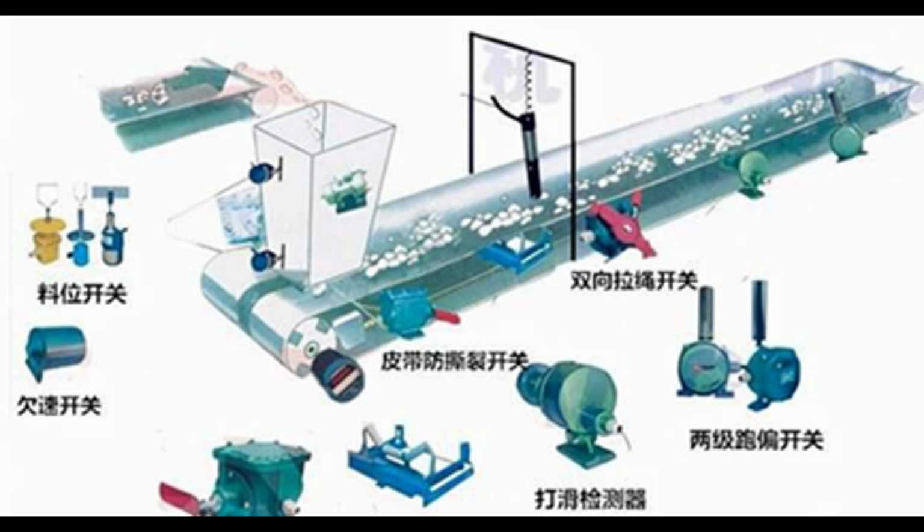3. Anti-tear protection device. An anti-tear protection device should be installed 10 to 15 m below the belt blanking point in the direction of the machine head when the head is driven. It is installed between the upper and lower layers of the conveyor belt, and the protection mode is piezoelectric or traction wire rope type. When longitudinal tearing occurs, the device alarms and terminates the operation.